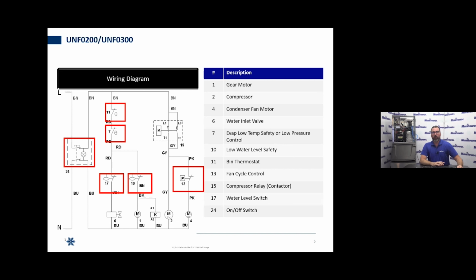We have fan cycle control, just like on most refrigeration systems that are using an air-cooled condenser. We want to be able to modulate that head pressure to control it, so we do have a fan cycle control pressure switch, and of course the condenser fan. Although it is crucial for that fan cycle control to work properly, that will not necessarily keep your machine from starting. So don't necessarily believe that a bad condenser fan motor is what's causing your machine not to start at all.